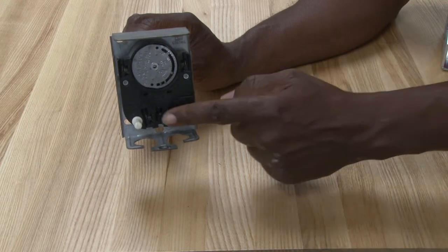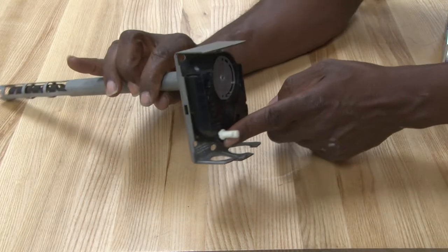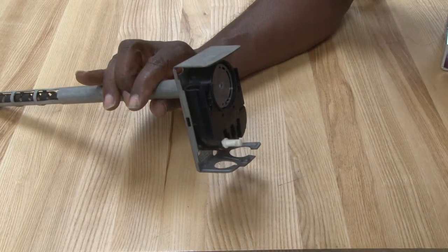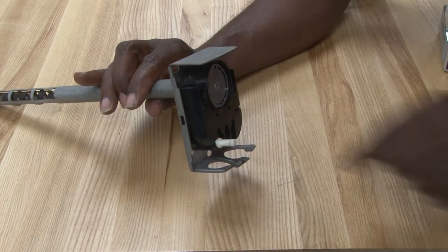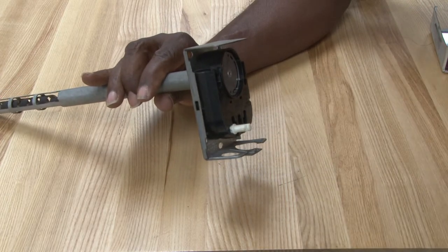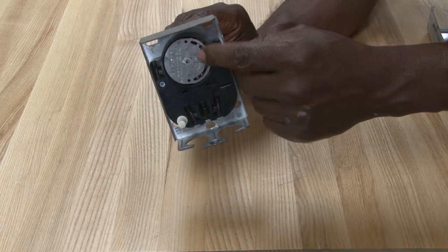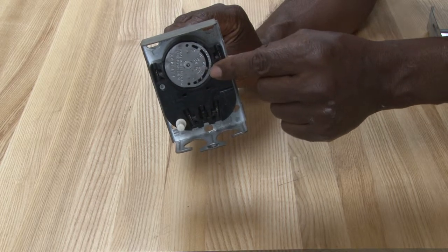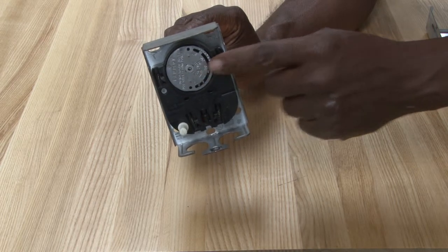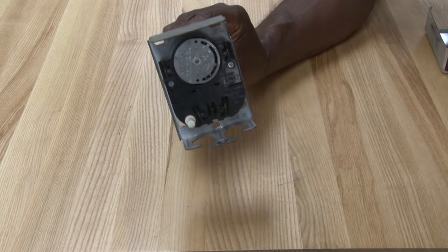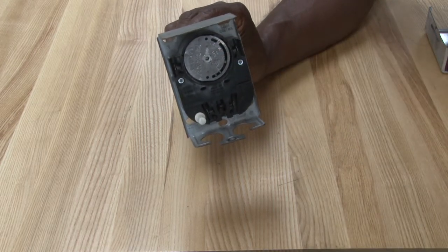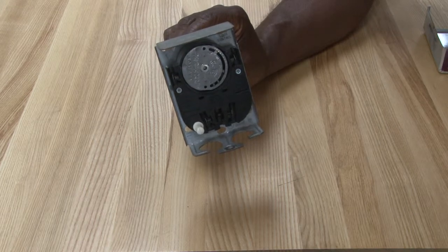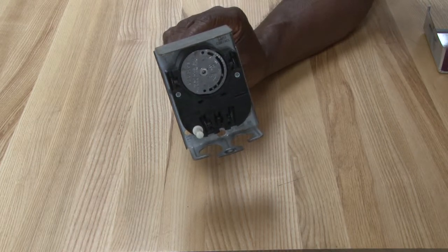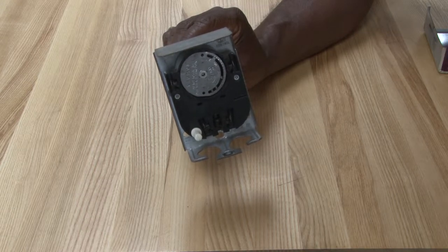And this particular one does have a special switch on it. It's a button that is used to control the blower in automatic position. We can turn it on and turn it off based on the position of that switch. This dial here is what the technician will adjust, these little slides, to turn the blower on and off at a predetermined temperature. Then there would be a fixed one for the high limit to cycle it off on the high temperature to turn the burners off. So one is cycling the fan, the other set of contacts is used for the high limit safety switch.